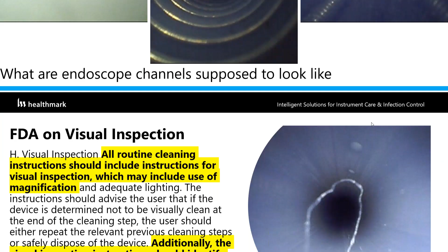Or, for example, when you purchase an endoscope, this is what it's supposed to look like, so you shouldn't have anything else. You may have some issues as shown from opening it up, but overall it should be free of defects. That should be the simple thing: when you receive something from the manufacturer, make sure to look at it to see what you purchased. As I said, especially since these are not inexpensive. They're $30,000 to $40,000 pieces of instruments. I know we used to check Dopplers, $400 or $500, but not checking this doesn't make sense.